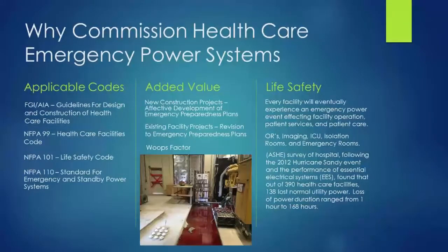What had happened is somebody had come in and worked on that day tank, and they shut off all the shutoffs and hit the bypass valves, and instead of allowing the fuel to go into the day tank, they inadvertently pushed it back up into the vent pipe, and the fuel was just being pushed out and spewing all over the room. What you see there is about a 6 to 8 inch housekeeping curb, and it's about halfway filled up with fuel oil. That was roughly 300 gallons of fuel oil that went into that generator plant at that time.